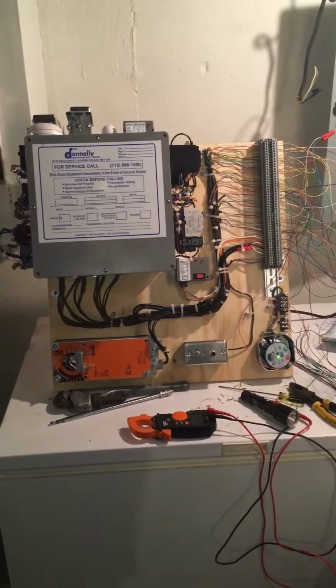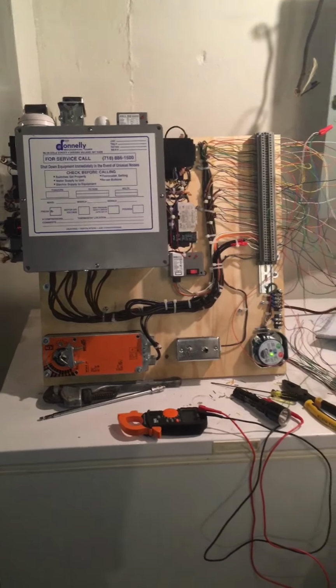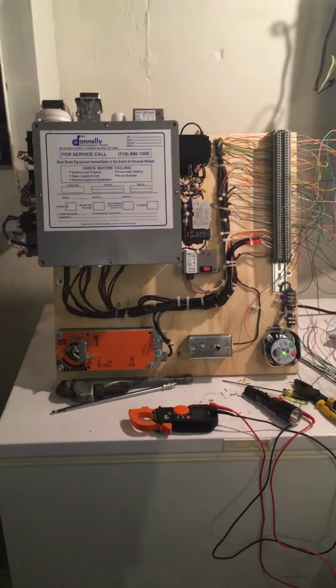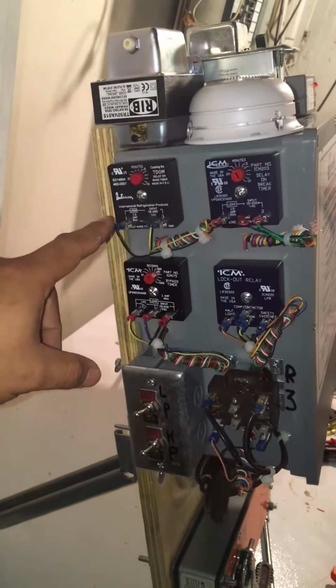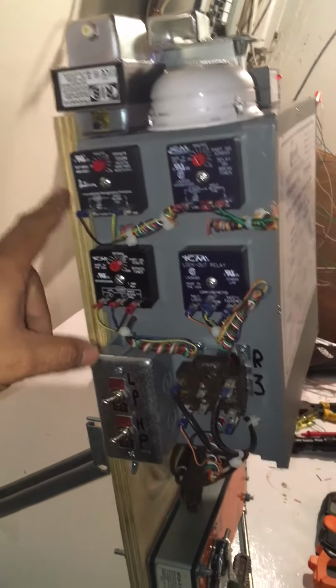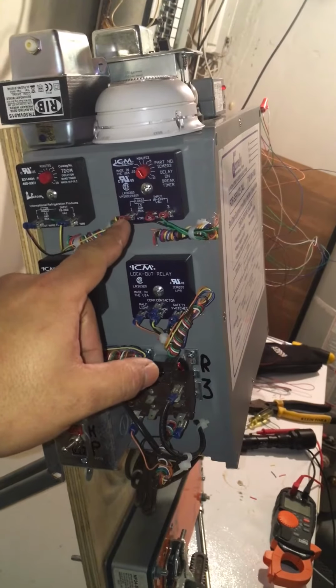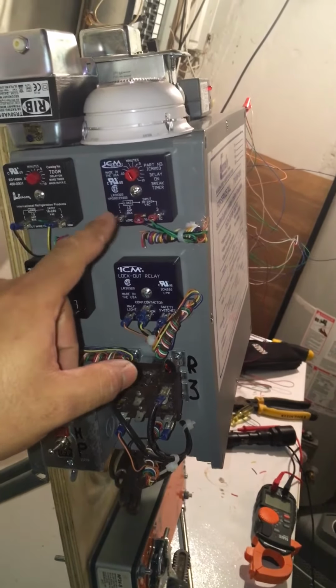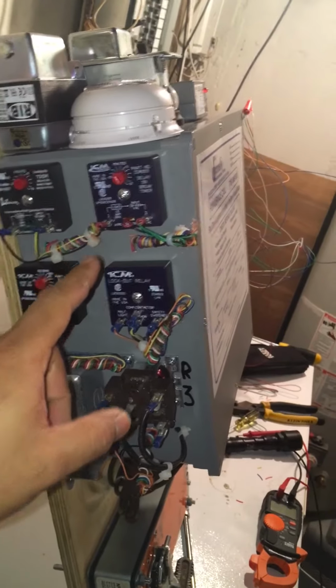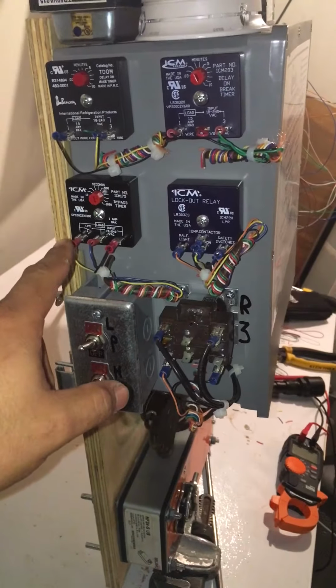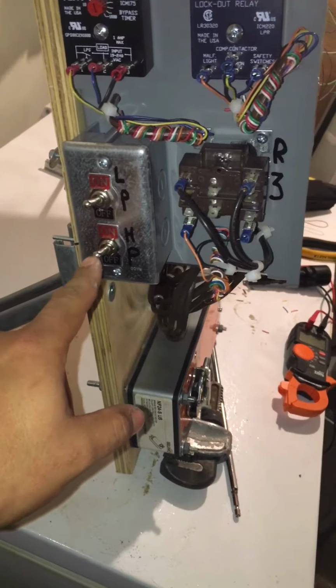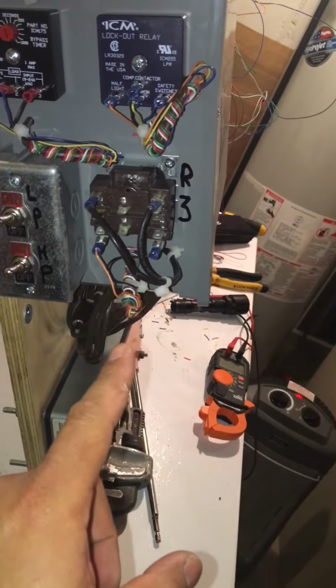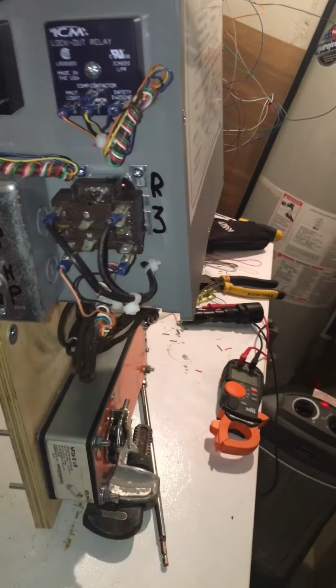Just finished completing the expansion of the control circuit board for the training class. Just to show a few things that we have over here. We have a delay on make timer, which is for a compressor. We have a delay on break timer, which is for the condenser water pump not turning on and off rapidly. Low pressure bypass timer, lockout relay, low pressure switch, high pressure switch, alarm relay, which I have labeled for R3.